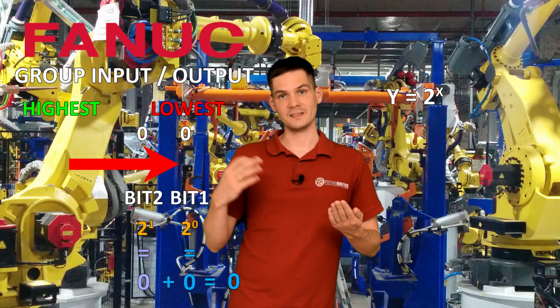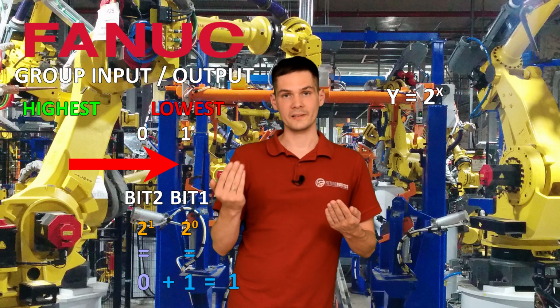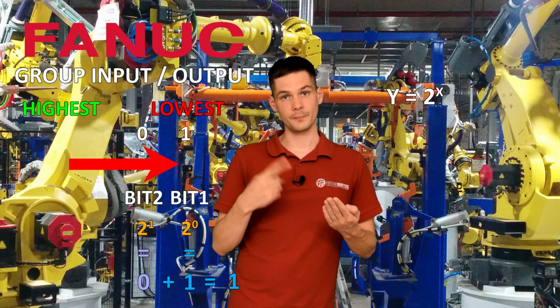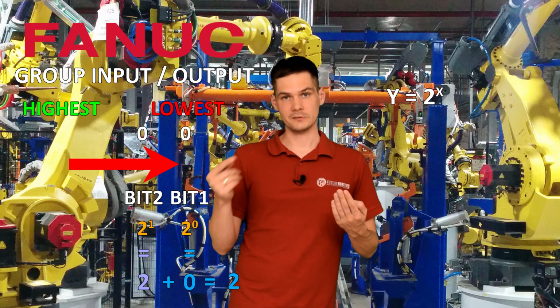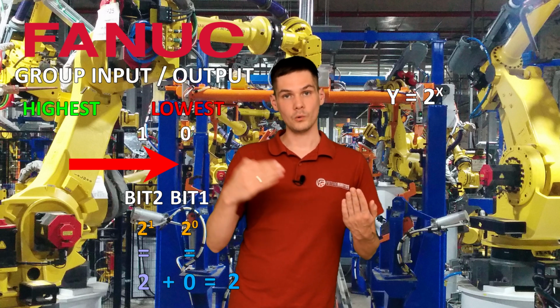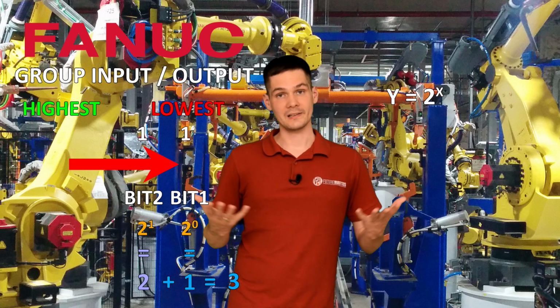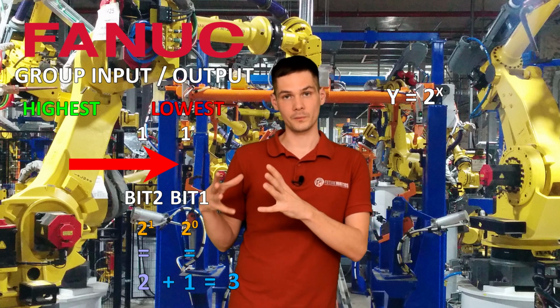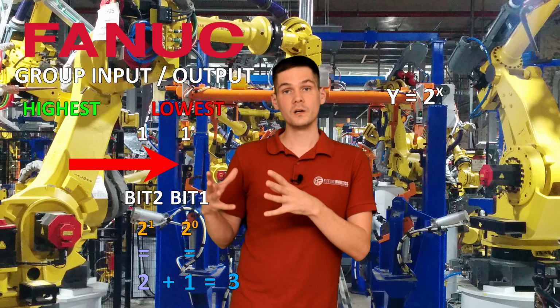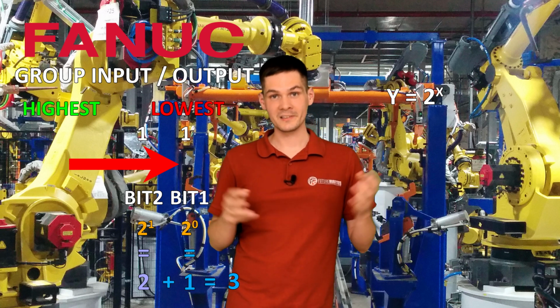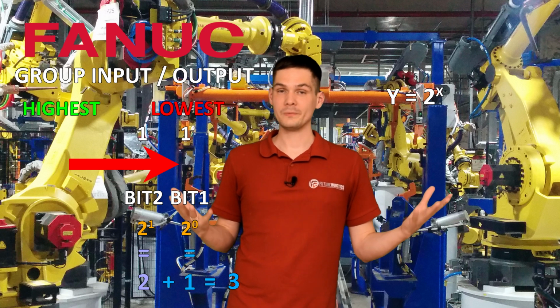If we send 1 and 0, then we're going to send the number 1. If we send 0 and 1, we're going to send the value 2. But if we send 1, 1, we're going to send the value 3. And that's how the group inputs and outputs work. They just translate the digital values from your digital inputs or outputs to a number using a binary translation. So that's pretty simple, I hope.